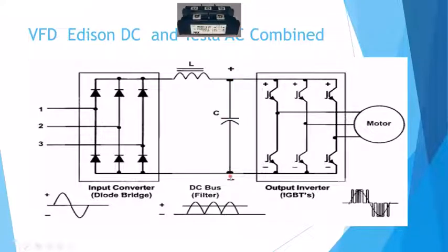The issue about the capacitors is, if you look at all the manuals of the various drives, they have about a 10 to 15 year life, depending on the design, because they get hot, cold, hot, cold, hot, cold, they dry out. And then after a period of time, they actually want to short out. So we haven't got that totally solved yet. They went to oil filled, but they have to be so much larger. But this is a weak component inside of a VFD, those capacitors after about 10 or 15 years old. So they do need to be checked towards the end of their life.